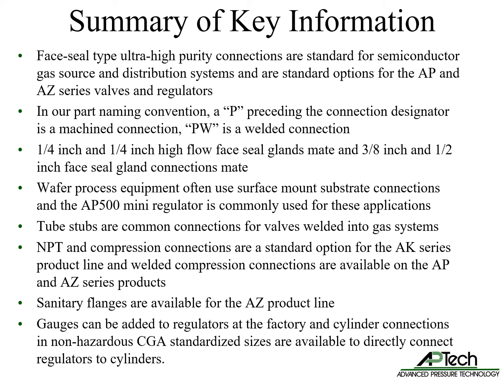To review the key information: face seal type ultra-high purity connections are standard for semiconductor gas source and distribution systems, and are a standard option for the AP and AZ series valves and regulators. In the part naming convention, P preceding the connection designator is a machined connection and PW is a welded connection. 1/4 inch and 1/4 inch high flow face seal glands mate, and 3/8 inch and 1/2 inch face seal glands mate.